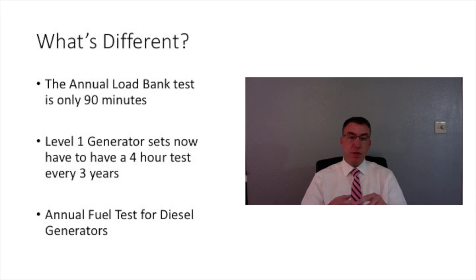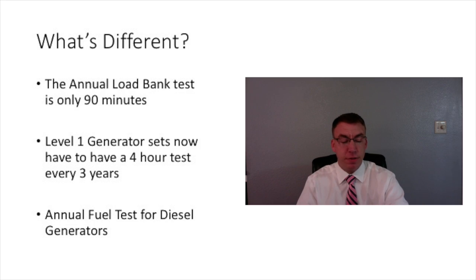Now, monthly load tests used to be, you just had to run it for 30 minutes monthly under load. Now it's 30 minutes under load after normal operating conditions. You can still do an annual load bank. Guess what? The annual load bank is only 90 minutes, not 2 hours.